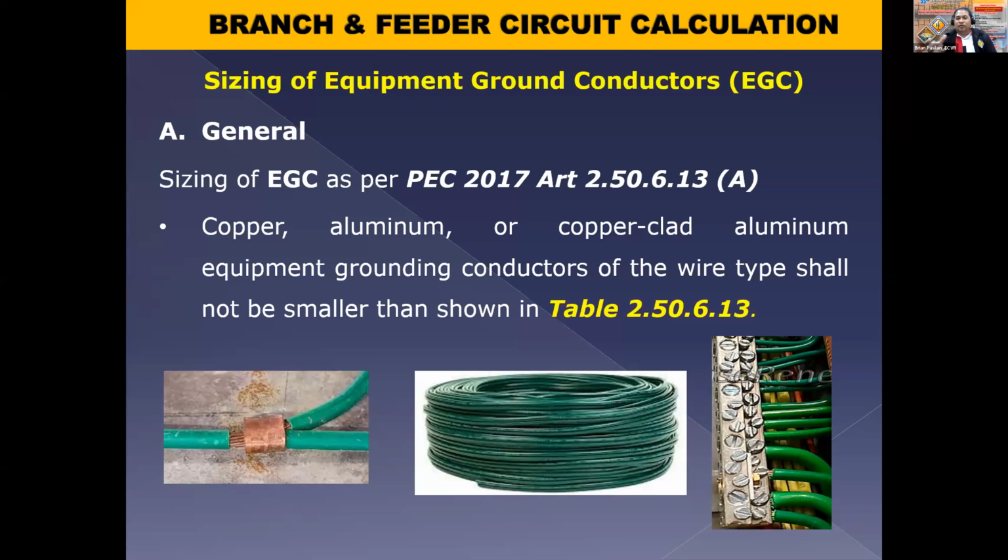So ang maka-influence dun sa impedance is the length of the conductor and size, no? So meaning to say, kung may system tayo na medyo mataas na yung run natin, then we have to conduct na talaga a ground fault study, no? To check on the impedance of the cable, kung enough current pa ba yung dadaloy during ground faults.